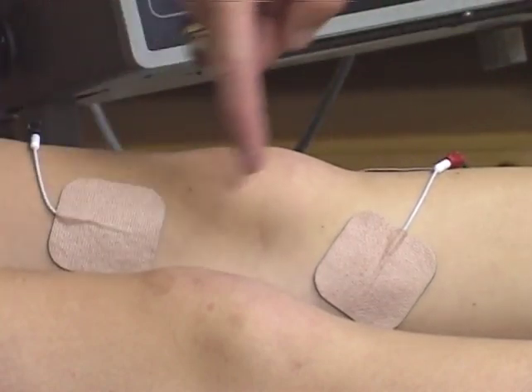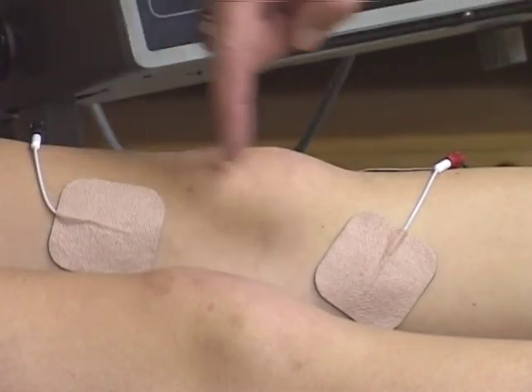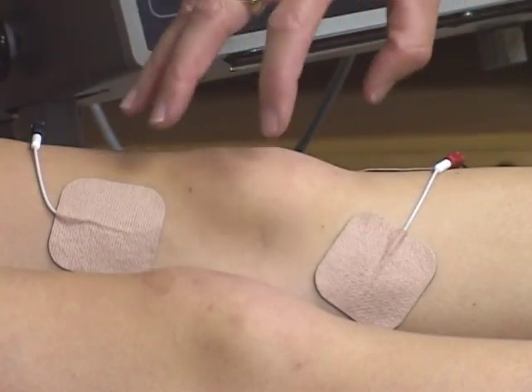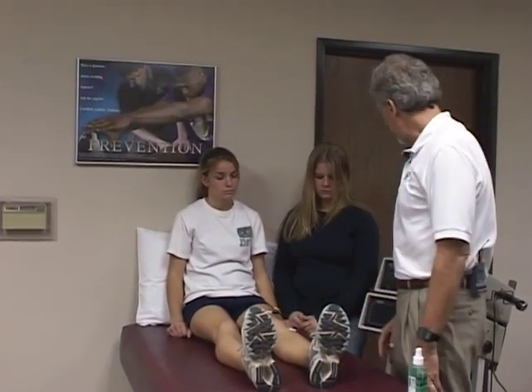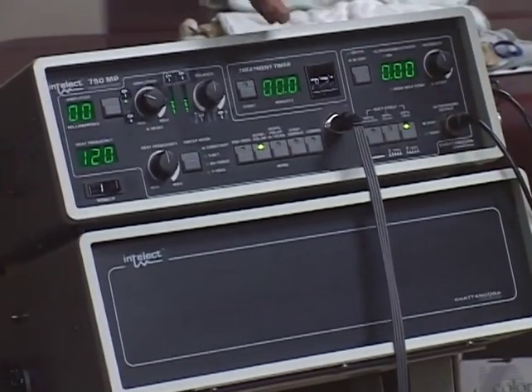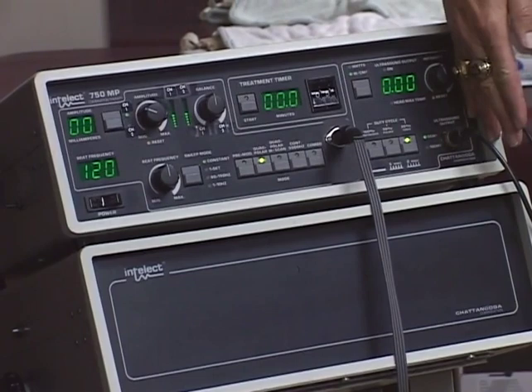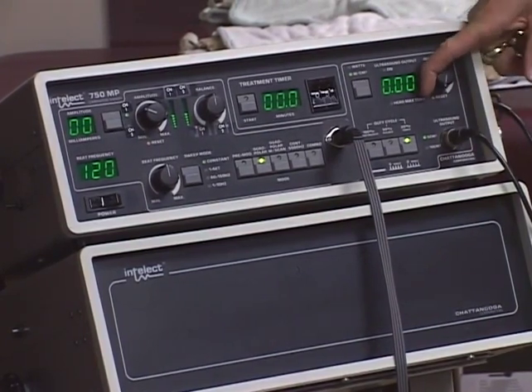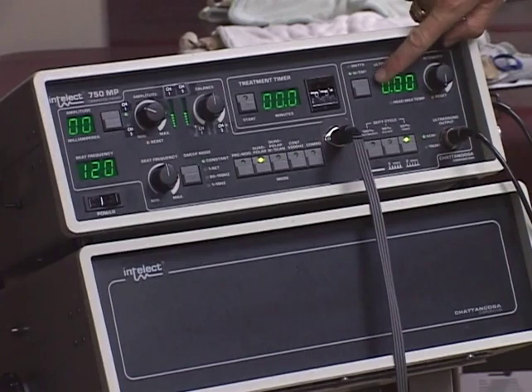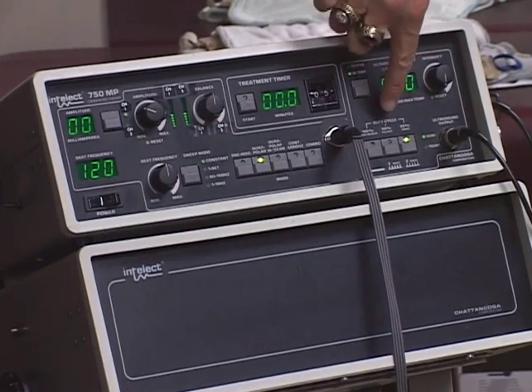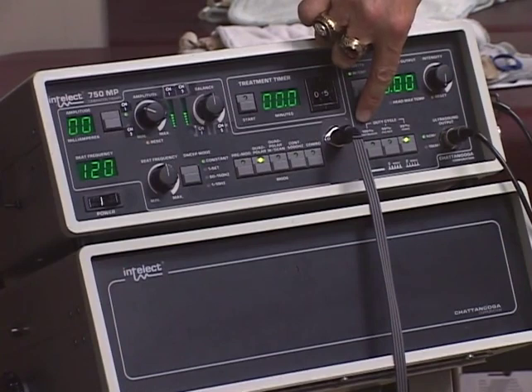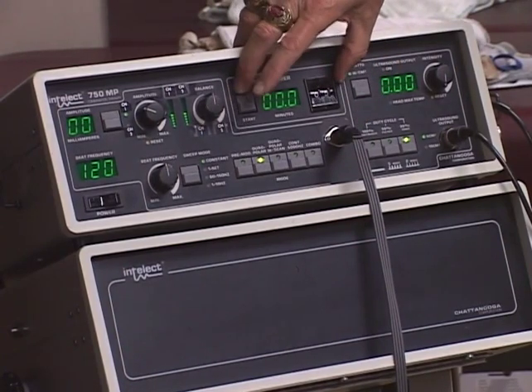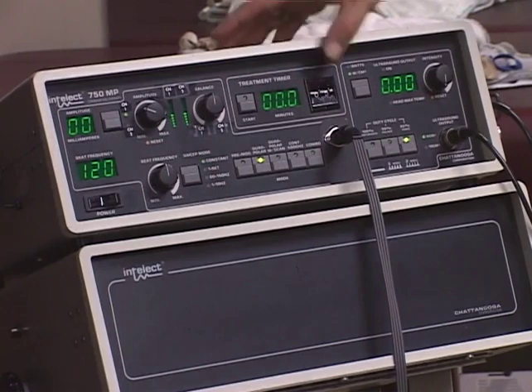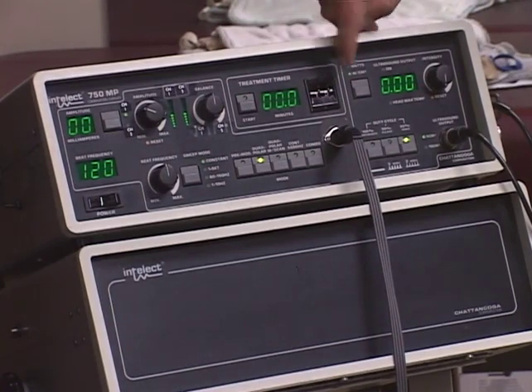What goes on is the black pads have their current going this way, and the red pads have their current going this way. And once again, everything here either increases or decreases the blood flow. We'll go ahead and set up the power switch. On this machine, like we saw before with the ultrasound, from this side over is the ultrasound. Here is how you adjust the intensity of the ultrasound. This is where you adjust the watts per cubic centimeter, and it's either 20, 50, or 100% of what you put out for the ultrasound. This is just for the timer specifically. Most generally, Amanda, we do about 15 minutes on these, so we're going to leave 15.